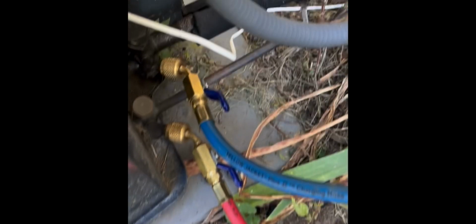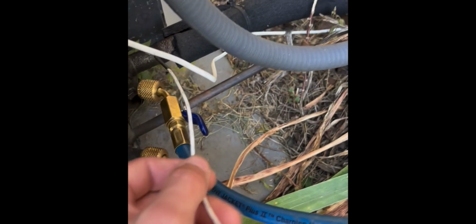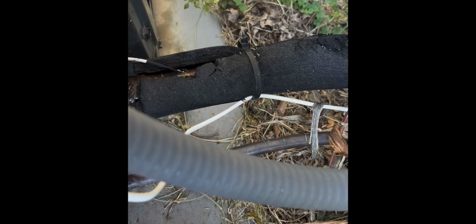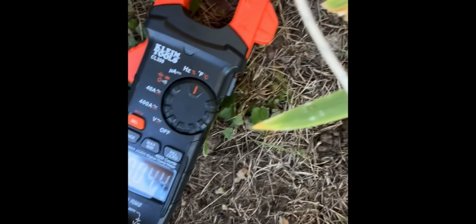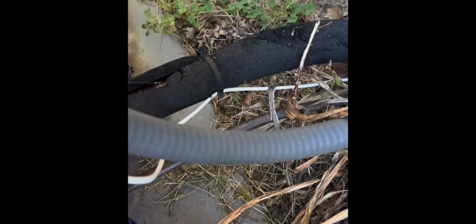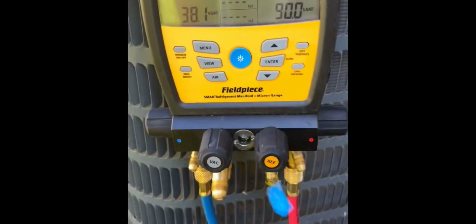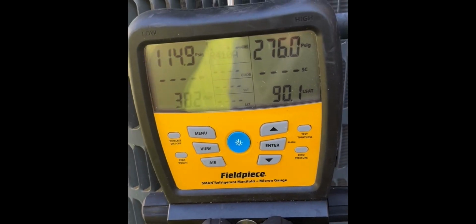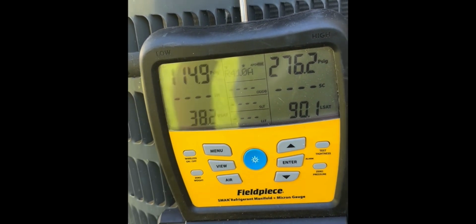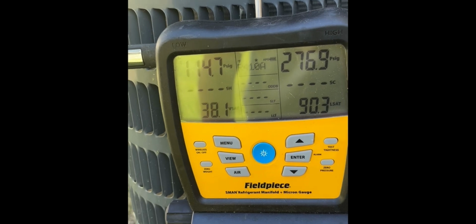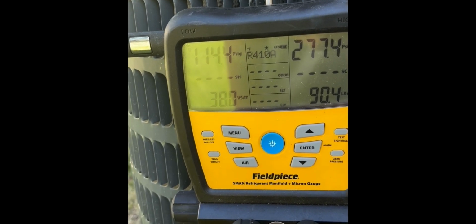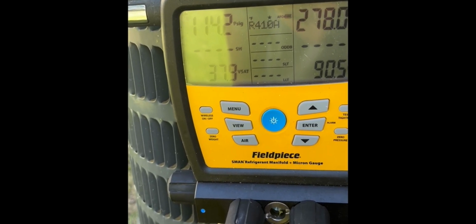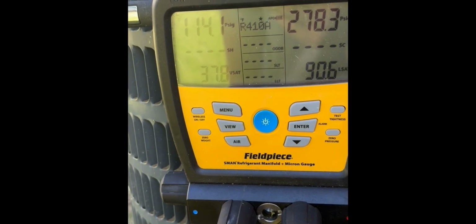Now to find superheat, you want to take the temperature of your thick suction line over here, using the probe. See there, we got about 45. And this is to find superheat. Now superheat is different. So we had about 45. You take the temperature you have on the line, minus your saturated temperature on your gauges here. So we had about 45 minus 38, that's about, we got 7 there. That's basically what we want for superheat, maybe one off, but that is about right.